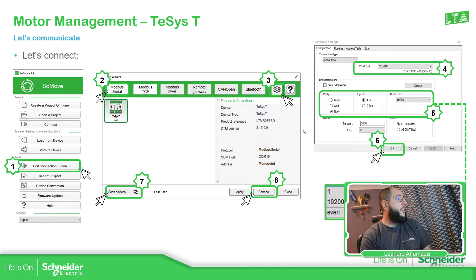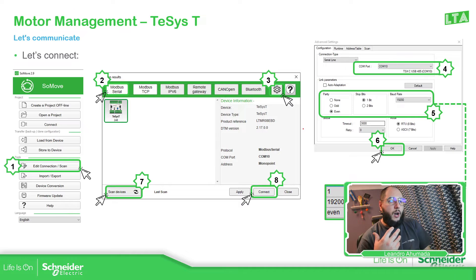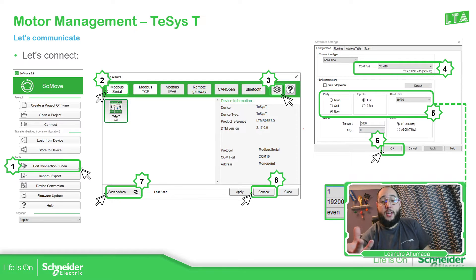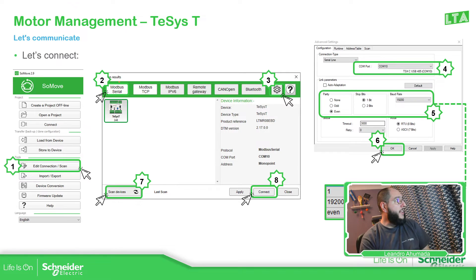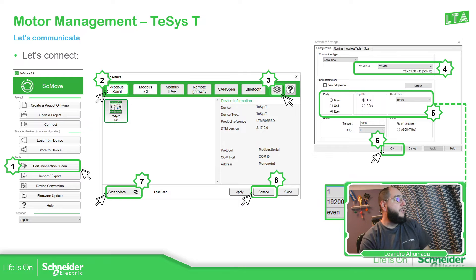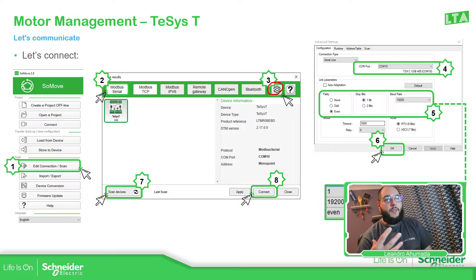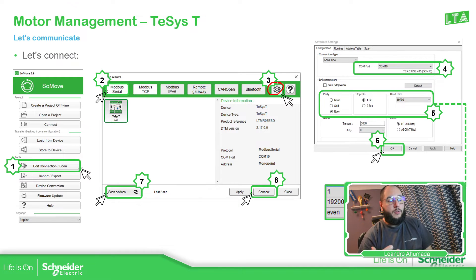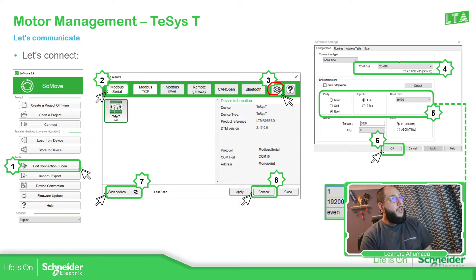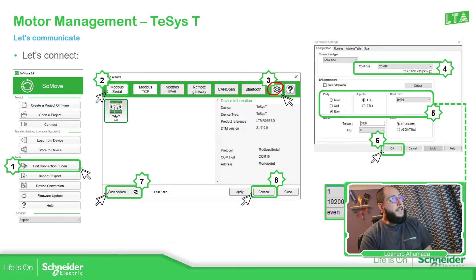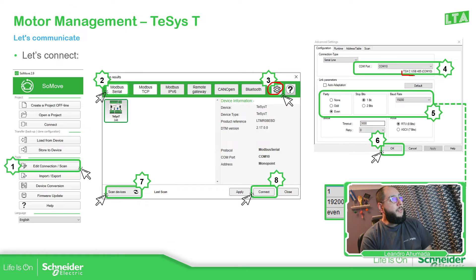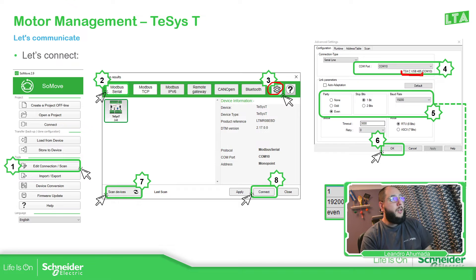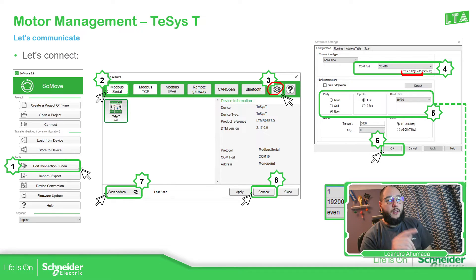Then the process is very simple. It's just, if we just want to upload information, just connect and see what is inside the device. We just need to edit connection and scan. Select Modbus as the way that we're going to communicate with the device. And then we need to click here on this gear. So we can configure the communication protocol on the port that we are going to select. In the COM port, you should be able to select yours. In my case, I have the COM port 10. It can be any on your system, but you need to find this.